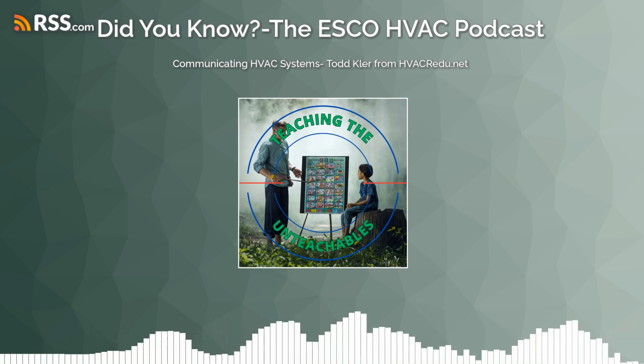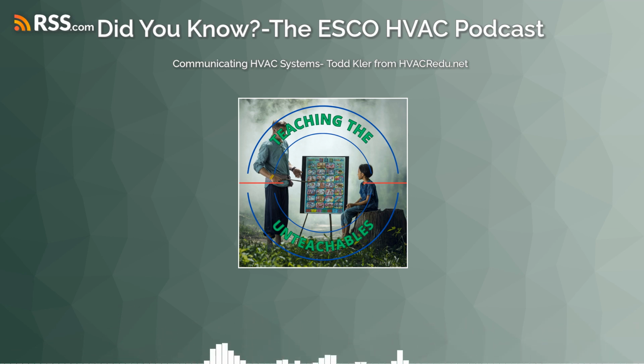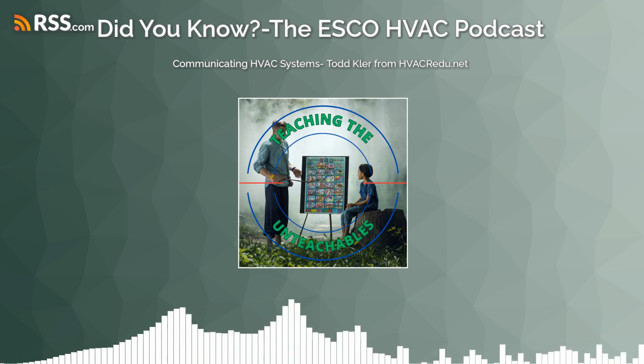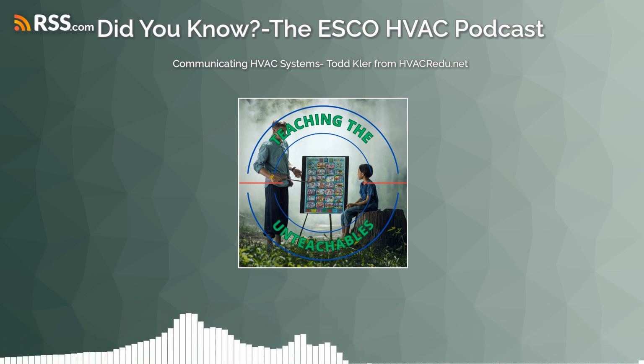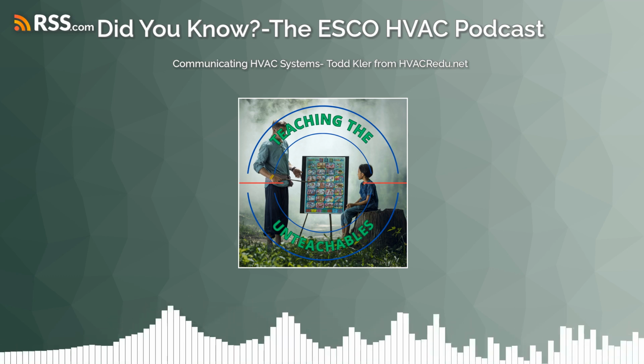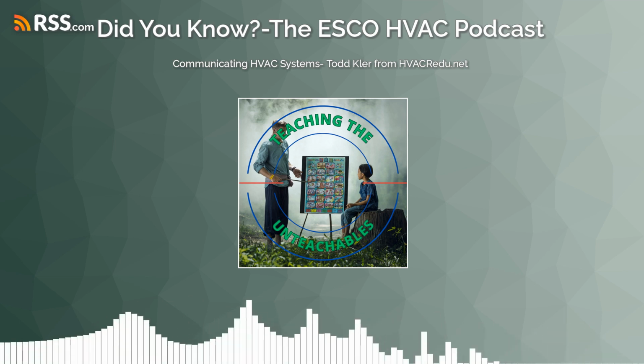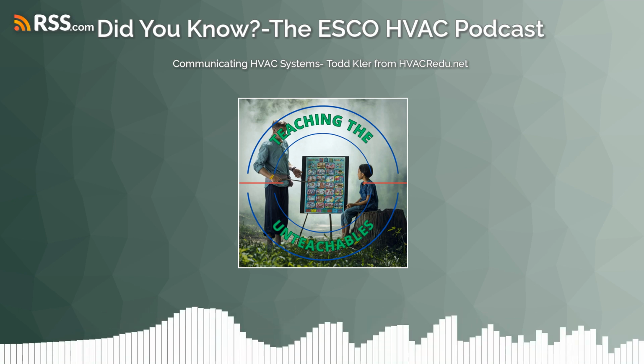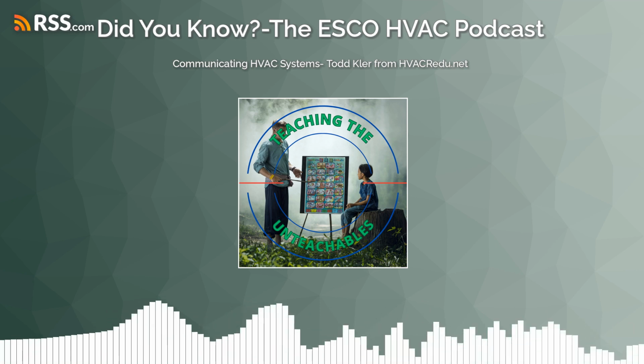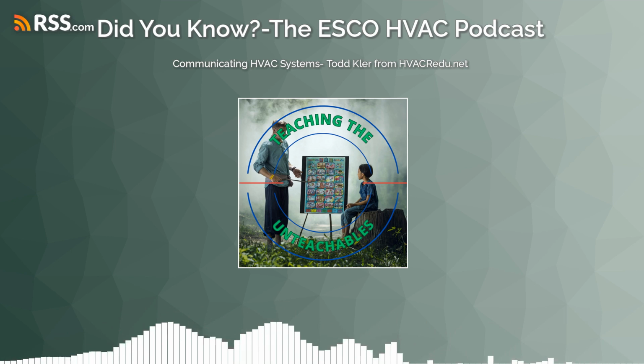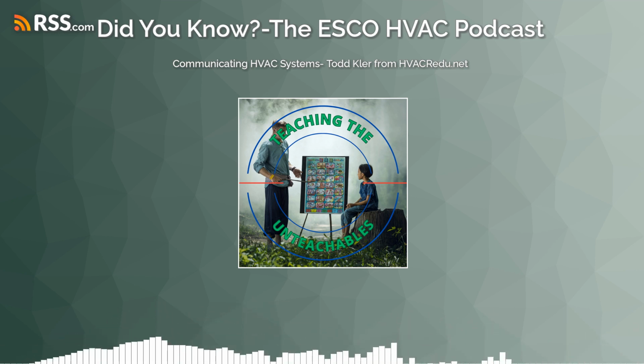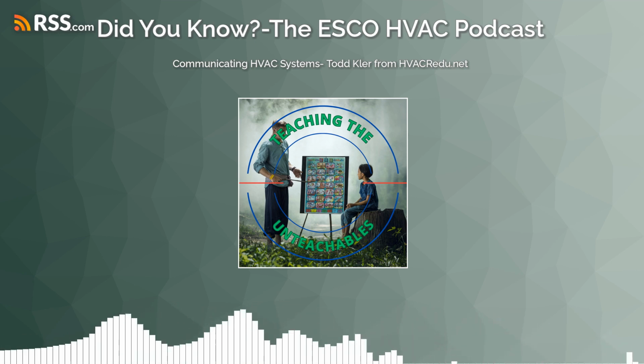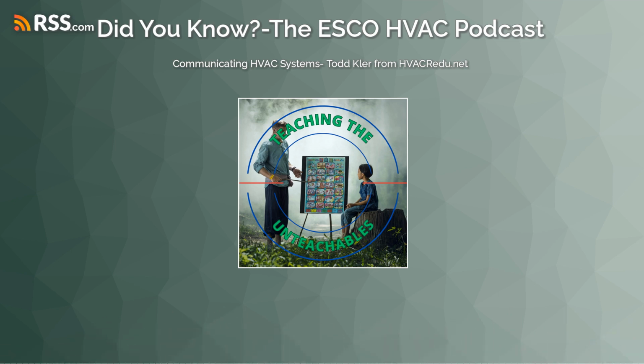Clean the wire. And I've seen on rare occasions, probably a handful of times, maybe half a dozen times throughout my career, the UFER, the residential or even commercial, the UFER got corroded, got water on it, and that UFER, that reference ground, that rod that goes 6-8 feet in the ground, was corroded. Yeah, absolutely. Remember on that AC system that was using 24 volts AC to run a contactor, it didn't care. It had enough AC voltage running to the compressor. Probably may not have been the safest thing in the world, but it didn't affect the way that our 24 volts AC operated contactor, but could absolutely with the communicating system. So I have had incidents where I had bad ground wiring that was not able to be reconnected properly. And so we would simply connect common from the indoor to common of the outdoor. Cannot use R because we already have a power supply at the outdoor unit on those, but we could use common as a backup.